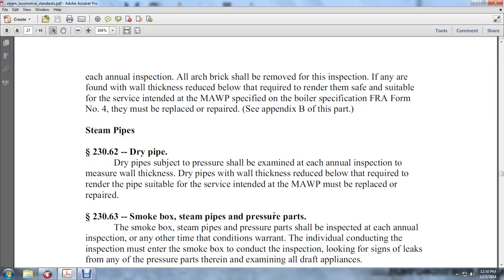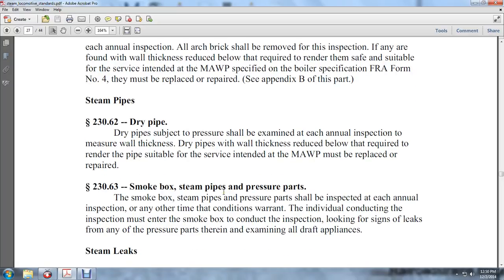Section 230-62, Steam Pipes: Dry pipes subjected to boiler shell pressure shall be examined at each annual inspection with wall thickness measured. Any dry pipe with wall thickness reduced below that required to render the pipe suitable for the service intended with the MAWP must be replaced or repaired.